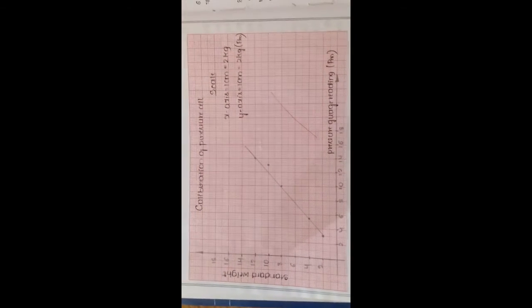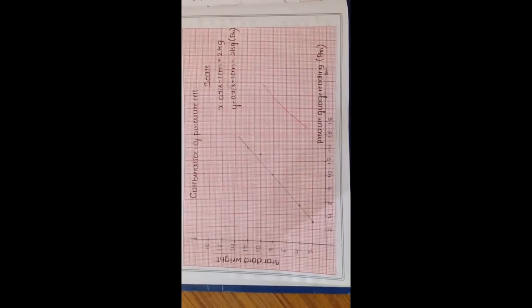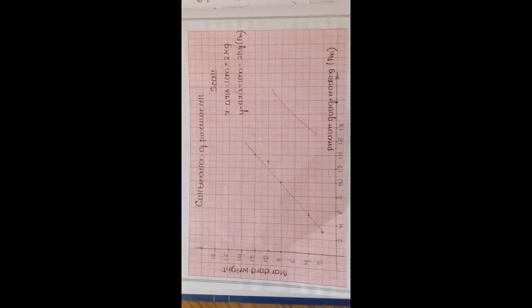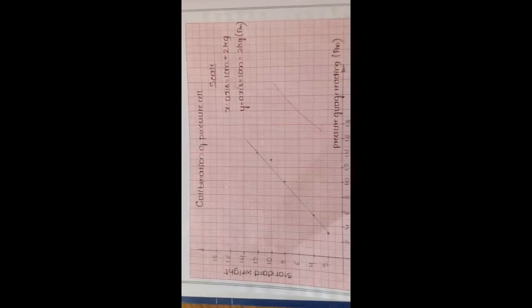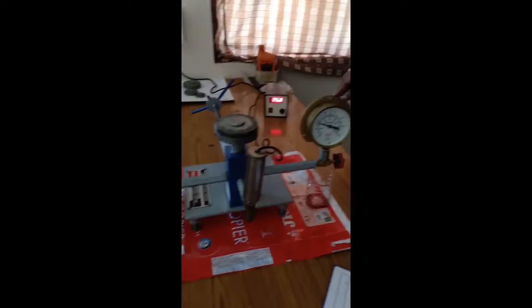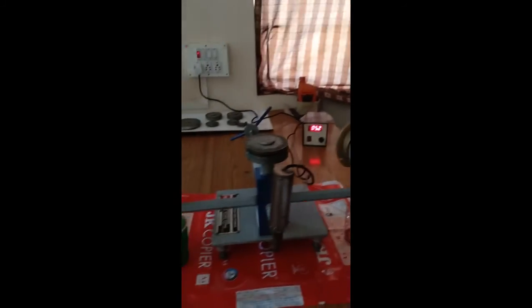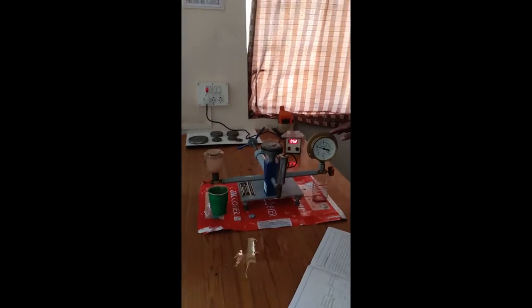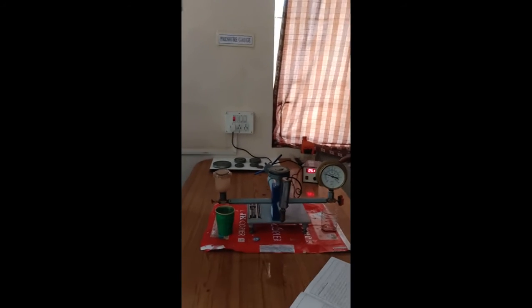Similarly, we need to plot the graph based on the standard weight and the pressure gauge indication readings that we get, and I am going to compare the pressure gauge with the load, to see whether calibration is required or not. Based on this percentage of error, we are going to calibrate the pressure gauge, to compare the actual values with the pressure gauge values that we get.